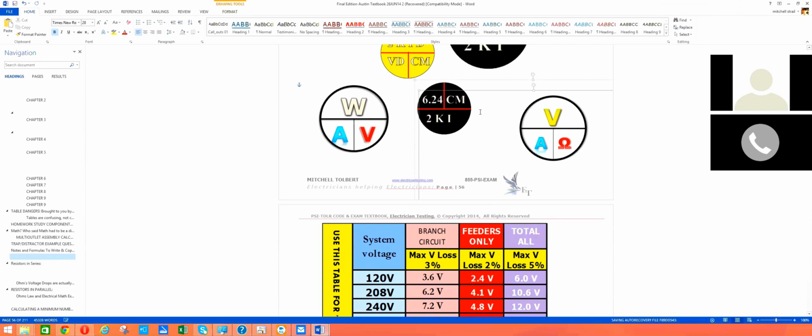And the next thing I need is circular mils, and circular mils is just a mathematical value for what our wire sizes are in a circular mill context, which is in the back. That same page that you were on just a minute ago, Chapter 9, Table 8. You'll find your circular mils there, and for number 12, it's 6,520. Is it 6520 or 6530? Going there right now. Page 767, I think, isn't it? Yeah, or 766. So you go down, 12 would be 6530. Right? 6530 sounds right to me too. So that's what goes in right here, 6530.